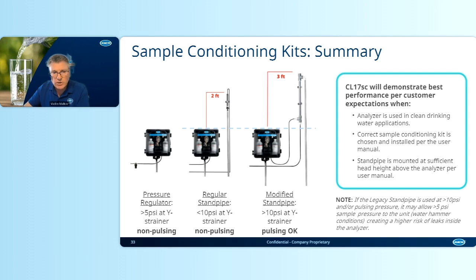Now, if you look at those three options on the left-hand side, of course, differentiation is with the pressure. The pressure regulator is a good option when there is a gravity feed with above 5 psi. The Y strainer regular standpipe is a good option for gravity feed and lower psi. Why am I saying gravity feed? Because this is non-pulsing sample delivery.